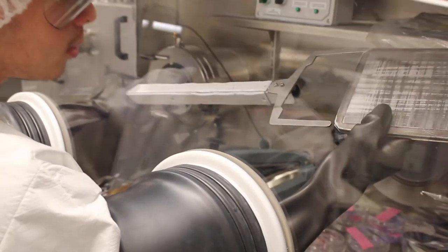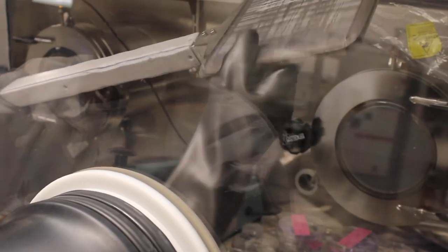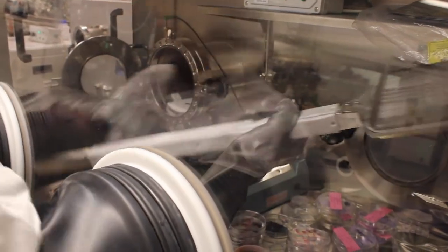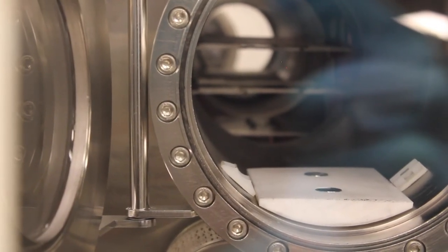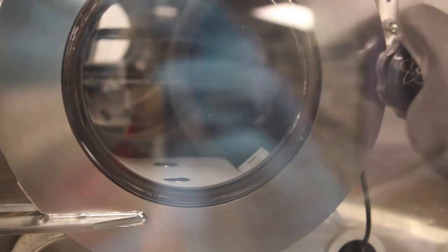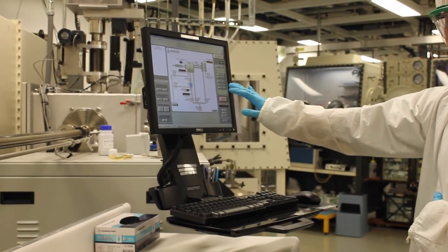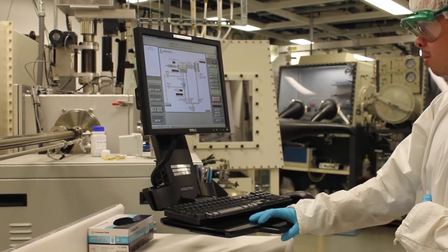So using a fork, we would now load this puck into a secondary chamber that we call a load lock. Now, the use of this secondary chamber is to provide an intermediate pressure environment between atmosphere and high vacuum. So the loading time into the chamber is much shorter than if we just opened the VTE chamber on its own. Once we close this door, we can pump down this load lock chamber externally using a computer, as you will now see. The entire operation of this tool is computer controlled. And with a pump down setting, we can begin the roughing stage for this load lock.